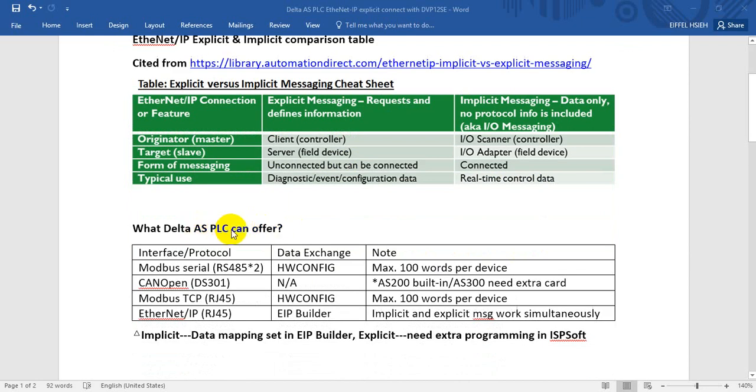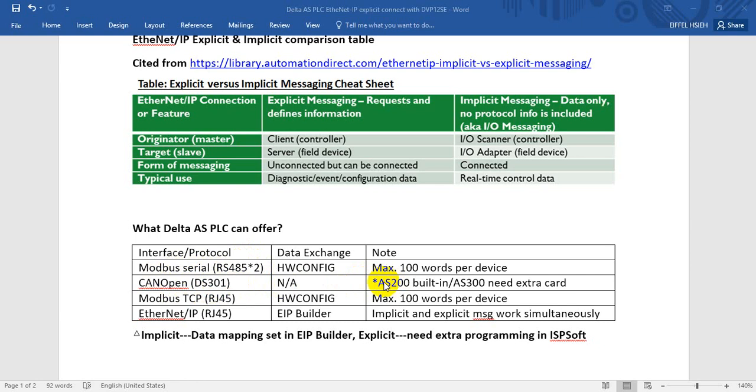What can Delta AS PLC offer for communication? Basically for AS PLC we have built-in Modbus serial port RS-485, we have two serial ports, then we have CANopen. We got DVP-B01 for the AS200, this one is built-in, and for AS300 we need to purchase a CANopen function card. For AS PLC it's also built-in Modbus TCP and EtherNet/IP.